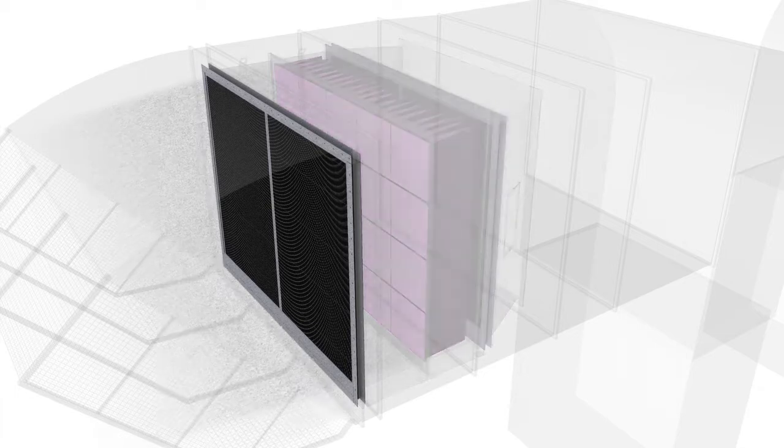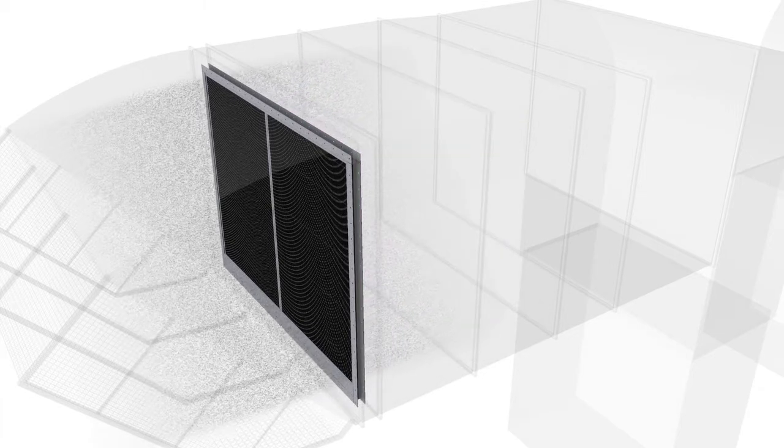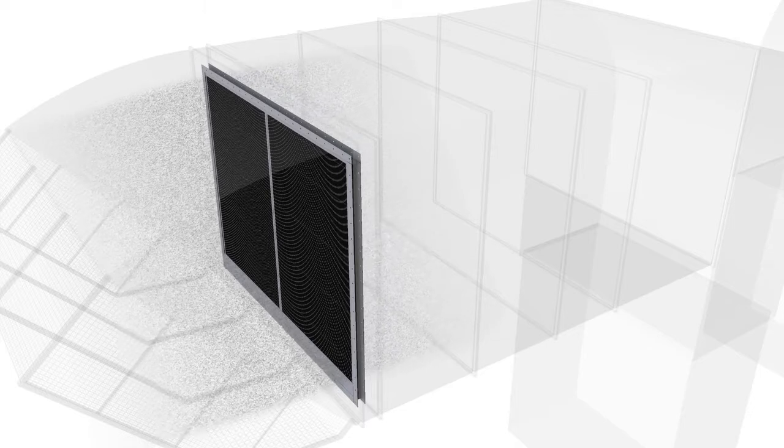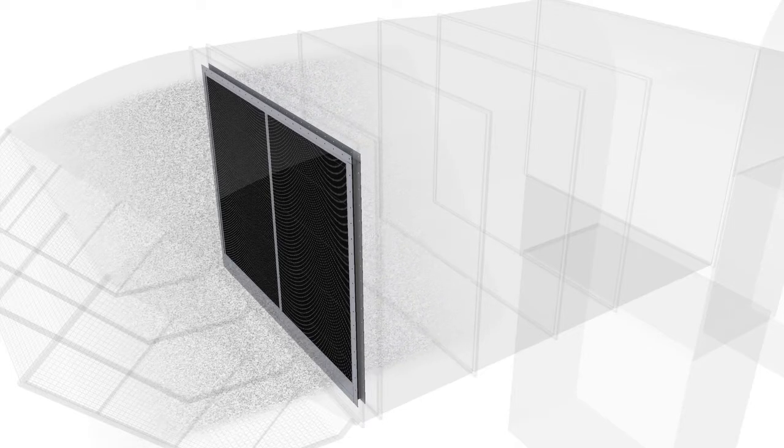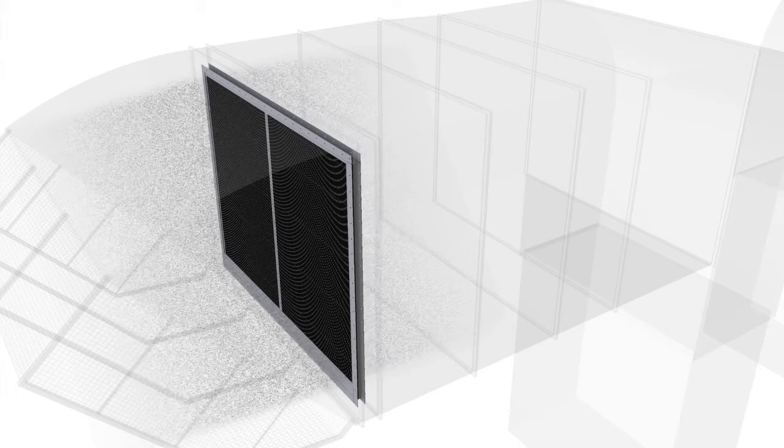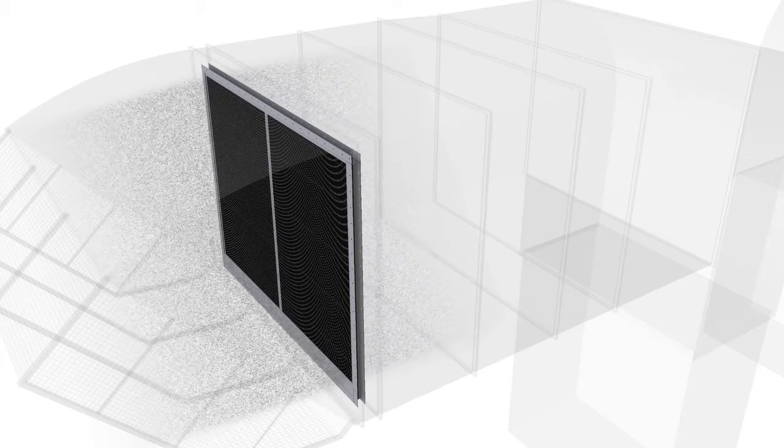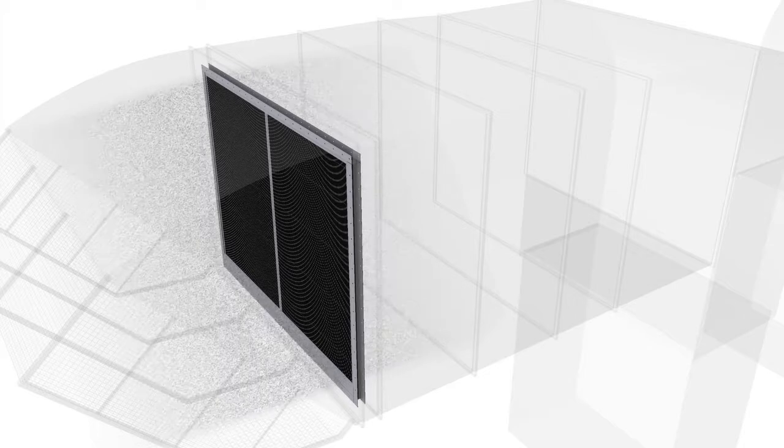Stage 1 is the vane separator. This stage provides a robust mechanical barrier to the filter house entrance and also provides bulk water removal of rain, sea spray and coarse aerosols, thereby protecting the later filtration stages from the harsh weather conditions you may experience on a platform or FPSO.